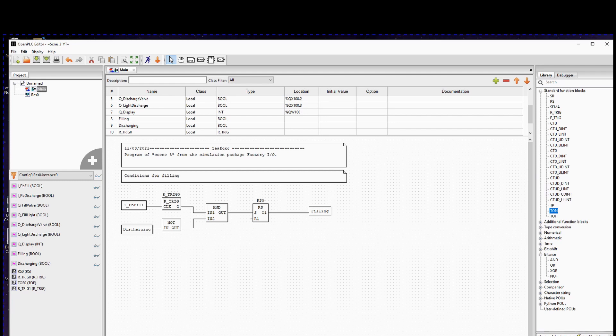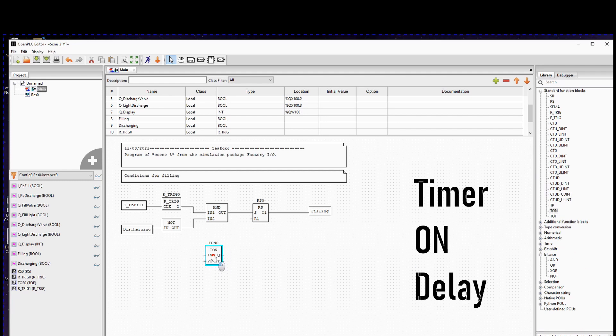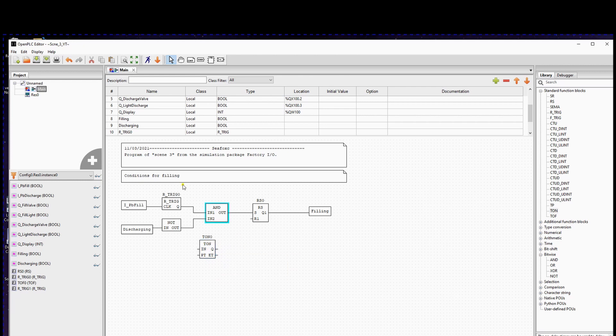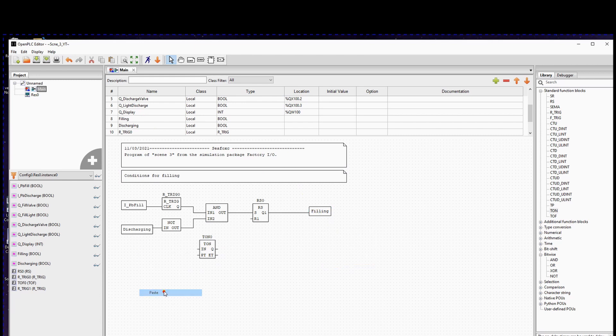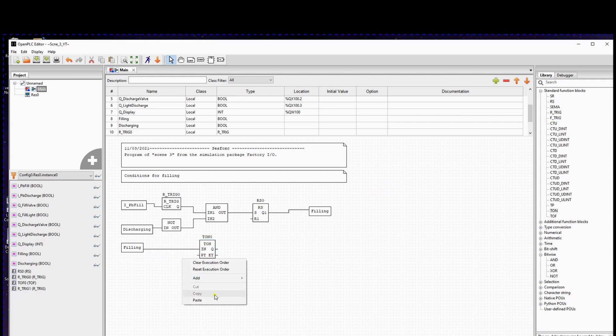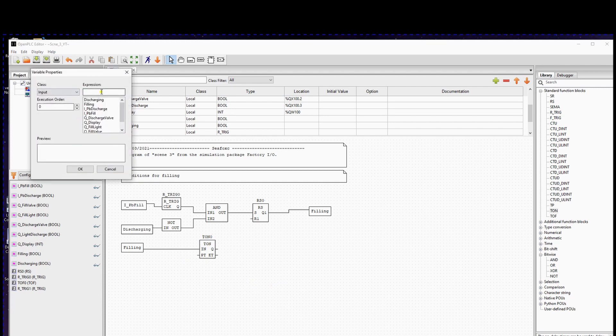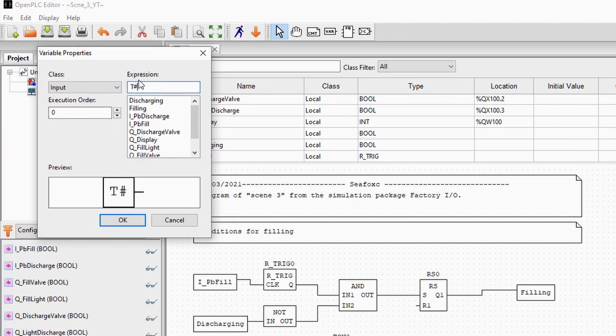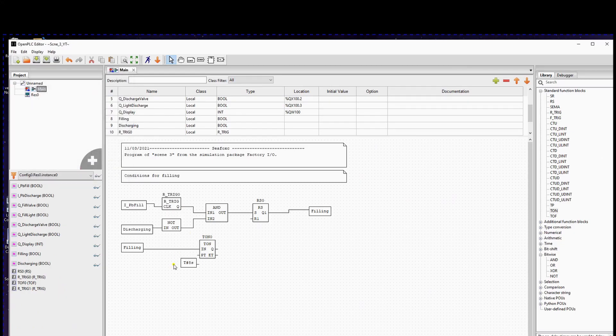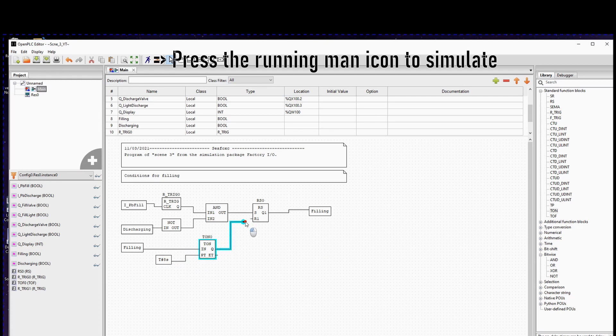To reset the filling state we will add a timer of 8 seconds. In this case we will use the TON timer. TON stands for timer on delay. The IN connection of the block is a trigger for the timer to start. We want to start the timer if the machine is in status filling, so we use the variable filling as an input to the IN connection. On the PT connection you have to set the time — how long before the output signal will be set to true. We will create a variable constant, set the data type to time using T, and specify 8 seconds. We connect the output of the TON function block to the R connection of the RESET block.